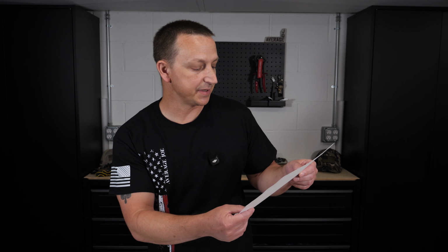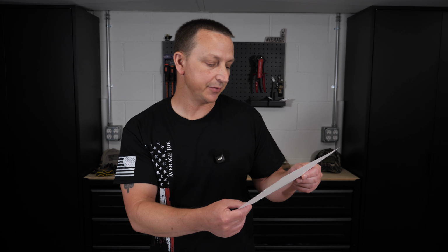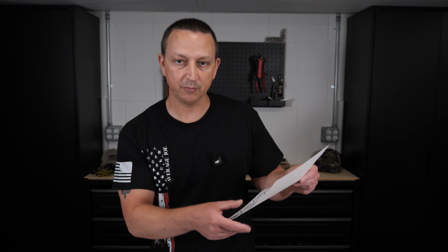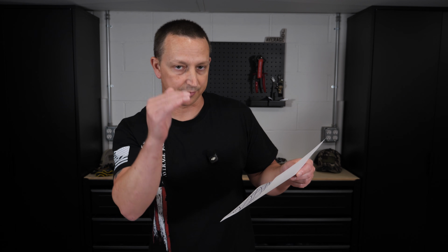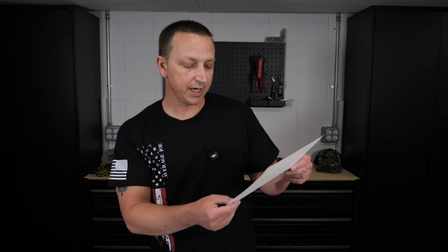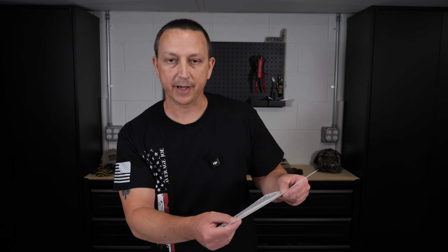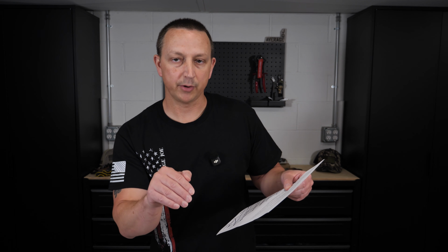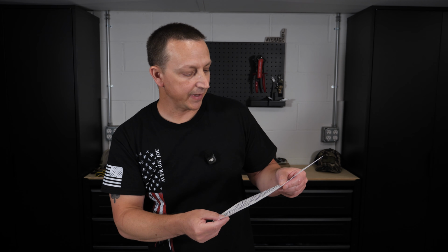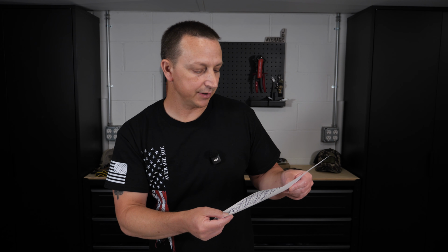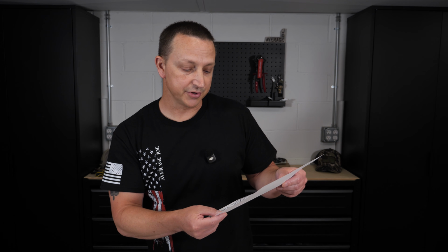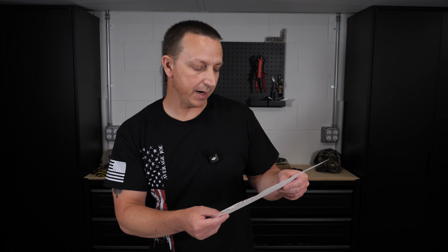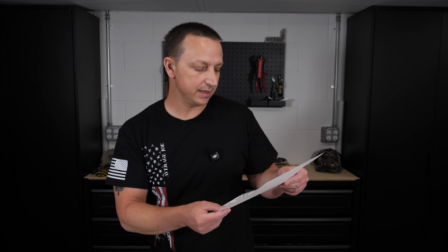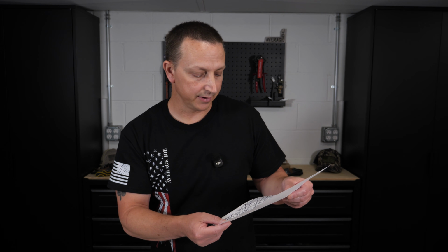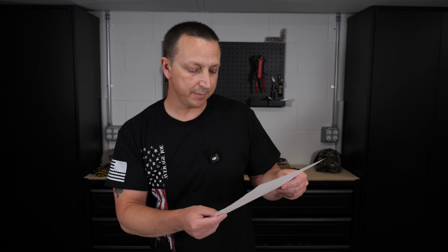Basically, try these steps. Please set all dip switches to the down or off position, which is 0 on the dip switches or all the way down. Then connect the short communication cable from the out port on battery number 1 to the in port on battery number 2. After that, only power on battery 1 using the power button. Battery number 2 does not need to be manually powered on, and its LEDs do not need to light up. Battery number 2 will be automatically controlled by battery number 1.